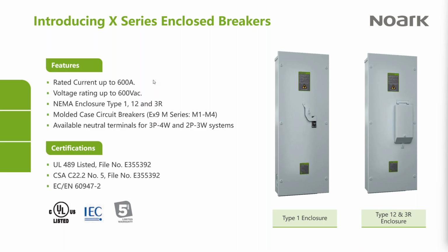Okay, so I think I've covered most of this. The current product that we have on offer is rated up to 600 amps, voltage rating to 600 volts, so it's good for every part of the North American market in Canada or the US. As I said, Type 1, Type 12, and Type 3R enclosures. And they use our molded case circuit breakers, the M series from M1 to M4. The M1 frame is up to 150 amps, M2 up to 250, M3 up to 400, and the M4 brings you to the 600 amp rating.